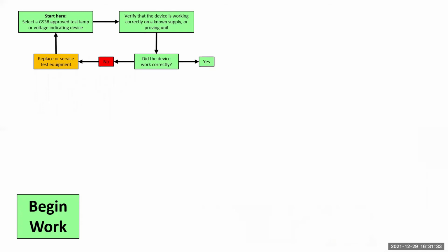If not, then you either replace or service the test equipment and try again. The reason I suggest proving this unit works first is to minimize the time between seeking permission, isolating the device, and proving dead. This is the point where the process is most vulnerable, as you may have covers off and more things can go wrong.